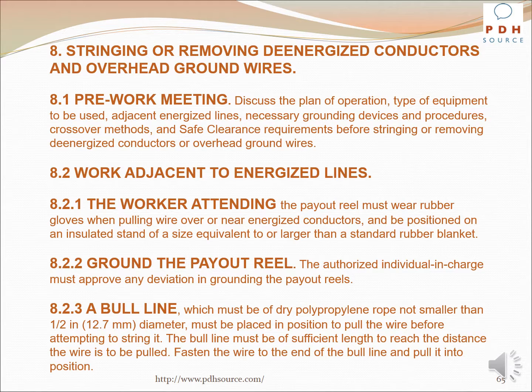A bull line, which must be of dry polypropylene rope not smaller than 1/2 inch diameter, must be placed in position to pull the wire before attempting to string it. The bull line must be of sufficient length to reach the distance the wire is to be pulled. Fasten the wire to the end of the bull line and pull it into position.